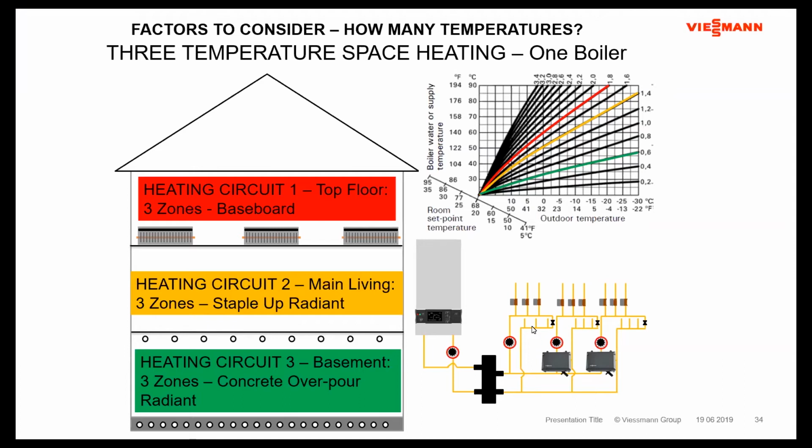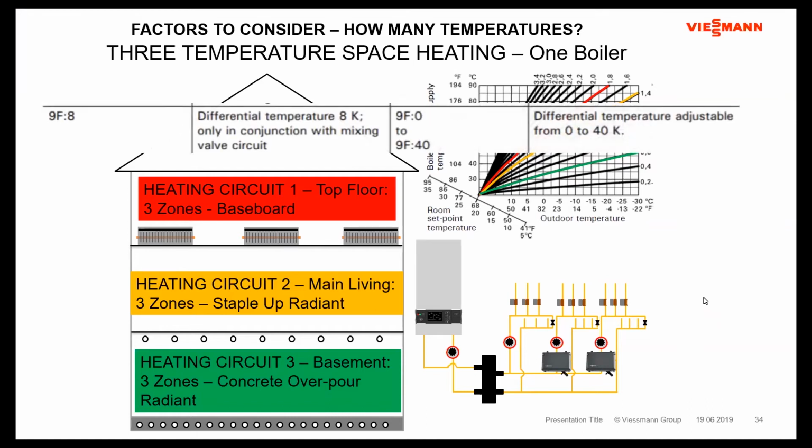As long as these systems are in operation, these valves are going to keep this system on a heating curve. Whereas if these are thermostatic mixing valves, we would follow the one heating curve for the high temperature until the temperature got so hot coming out to this that the thermostatic mixing valve would throttle that back and make some return temperature to it. So it's not really a true reset type of component.